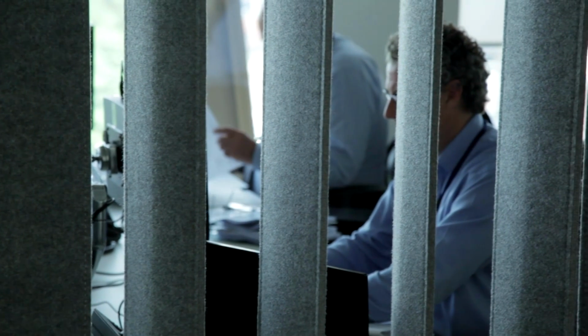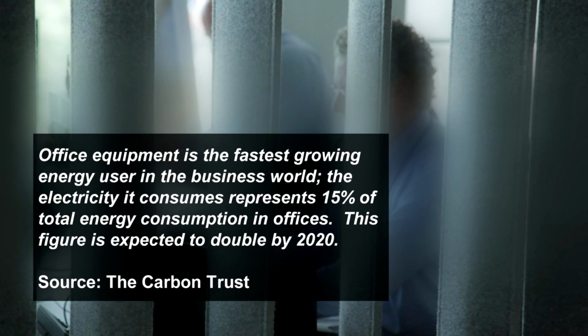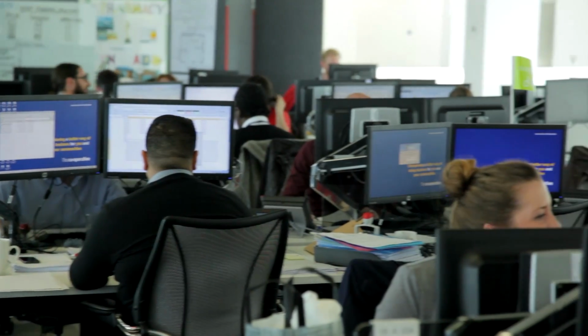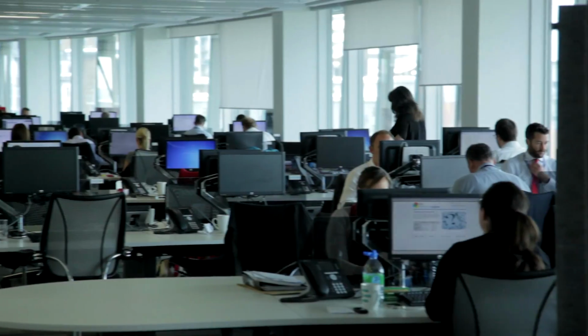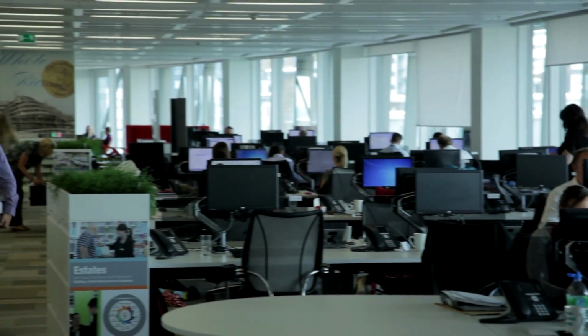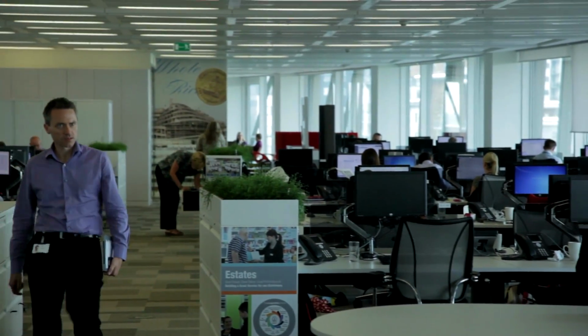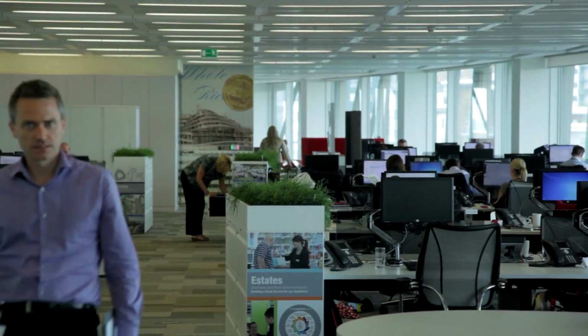With some 3,500 people working in the building, the use of computers can be a huge strain on that power supply. According to the Carbon Trust, office equipment represents 15% of total energy consumption in offices, a figure it says could double by 2020. So the strategy that you see in place within the building is what we term thin client. So they have what you would call, for want of a better phrase, dumb terminals on their desks. So all the processing, or the vast majority of the processing, is contained within central server areas where that is cooled and the heat energy from there is dealt with separately.